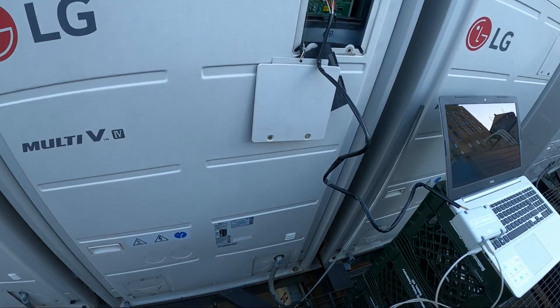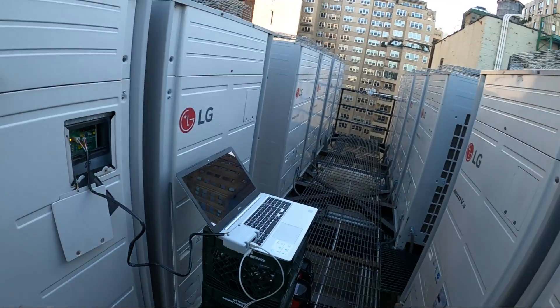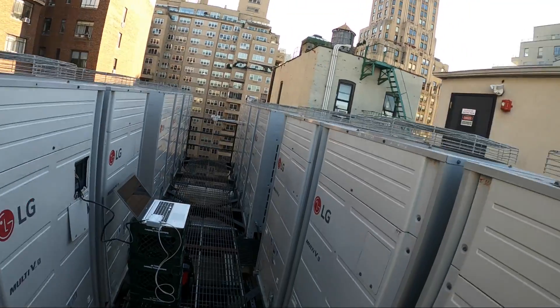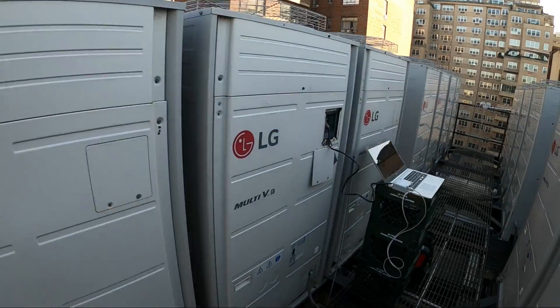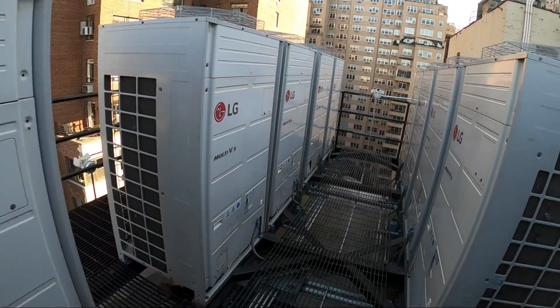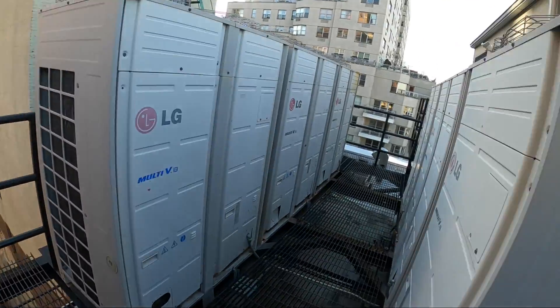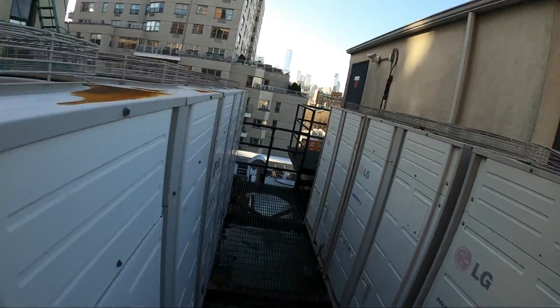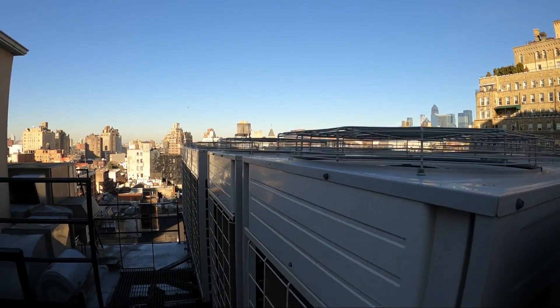Running on very high amps is a serious problem — that's why the compressors keep going. We have quite a few units here: left and right, compressors are failing. It's not only this unit; we've got more units down here too. These are the Gen 3s and everything here is Gen 4.